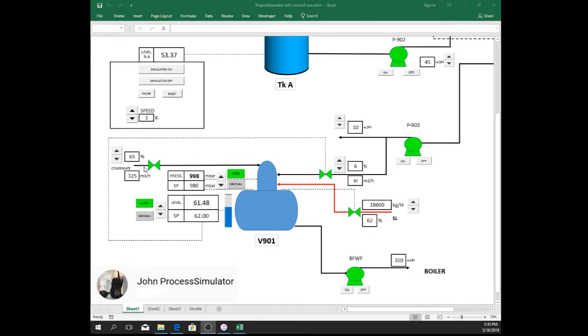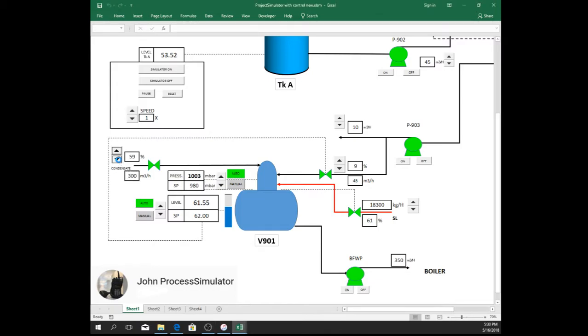If we reduce the condensate return by reducing valve opening, let's say make it 60 or 55%. This valve should react and now it increased to 16%. This is to maintain the setpoint of 62%.